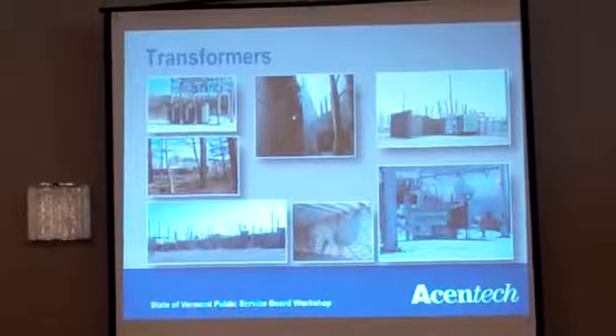The good news is transformer design has come a long way, with much better metals. People are willing to put more copper into them and oversize them, reducing the fluctuating, alternating fields inside so you don't get as strong a vibration initially. That comes with money, but a higher efficiency transformer gives you less noise—typically 10 dB or more just coming along for the ride if, as the owner, you choose to buy a higher efficiency transformer, since you get a payback from more efficient gear.